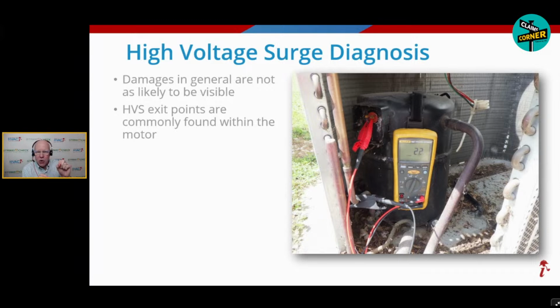The energy is not supposed to be going from the terminal and be able to go to ground. Something inside this motor now is touching that shouldn't be. The windings are touching each other, or the windings are touching the metal case. Something's going on, and we've had a major event inside this thing to let that happen. And now the technician has to go to the next step and figure out, well, was that an electrical event? Was that a lightning event? Was that a mechanical breakdown? Was that something else? Right.